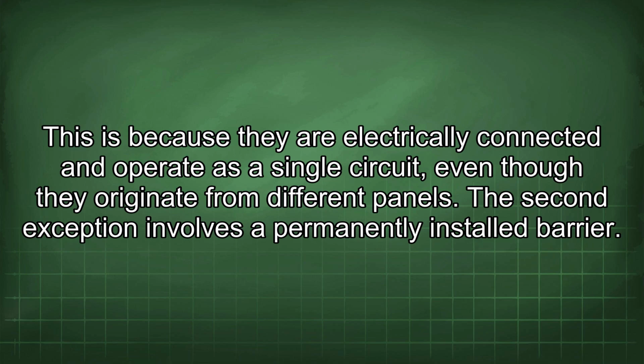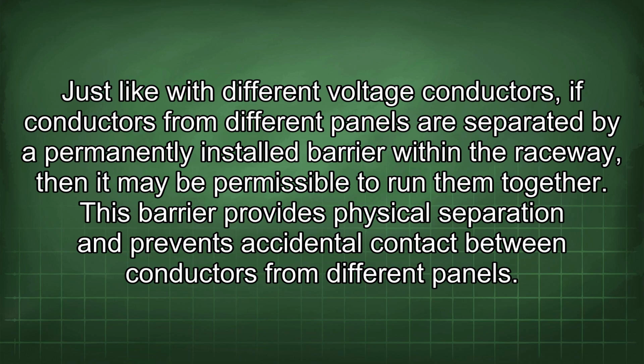The second exception involves a permanently installed barrier. Just like with different voltage conductors, if conductors from different panels are separated by a permanently installed barrier within the raceway, then it may be permissible to run them together. This barrier provides physical separation and prevents accidental contact between conductors from different panels.